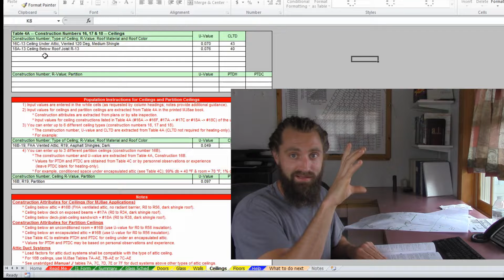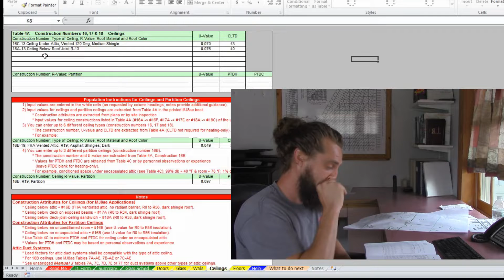Again, if I go over here to construction number 18, that is where we're dealing with ceiling below roof joist. You would go down through here, you'd find your construction number based on the insulation that you know is in that cavity. I don't know, but I'm just assuming that it's probably like an R13 because it's not a lot. Then you would associate a U value with that.